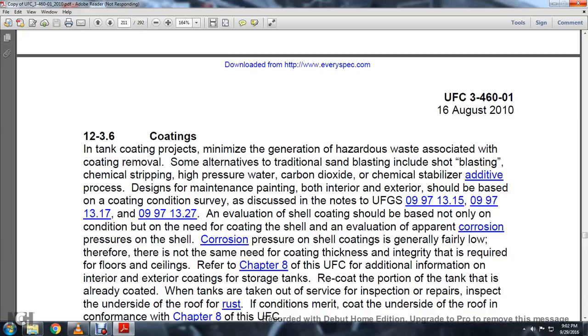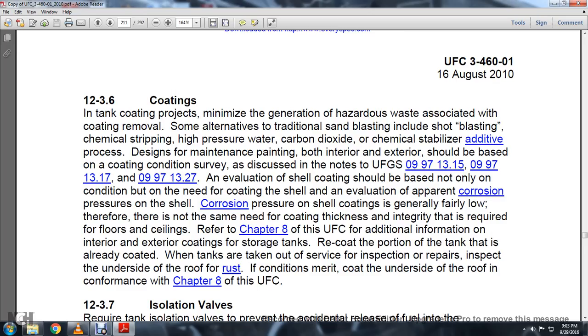Section 12-3-6: Coatings. Tank coating projects should minimize the generation of hazardous waste associated with coating removal. Alternatives to traditional sandblasting include shot blasting, chemical stripping, high-pressure washing, carbon dioxide, or chemical stabilizer additive process. Maintenance painting decisions should be based on a coating condition survey, referencing UFGS sections 099713.15, 099713.17, and 099713.27. Evaluation of the shell containment coating should consider not only coating condition but also corrosion pressure on the shell. Refer to Chapter 8 of the UFC for additional information on exterior coating of storage tanks. Re-coat portions of the tank already coated when the tank is taken out of service for inspection or repairs, and inspect the underside of the roof for rust.